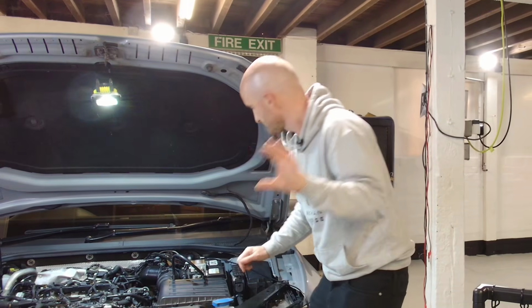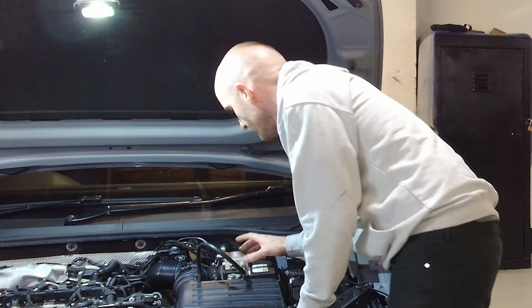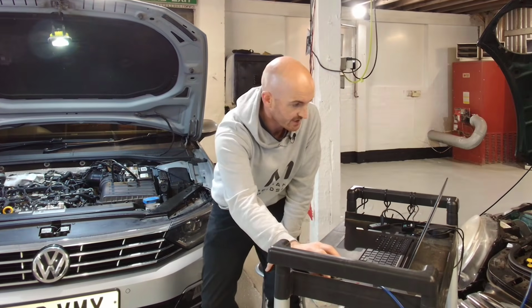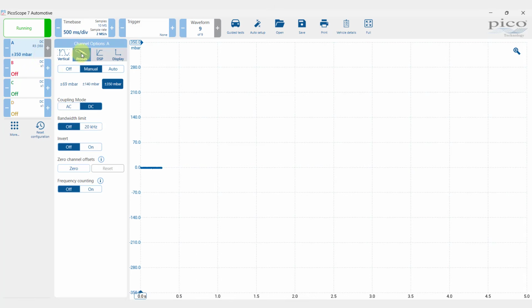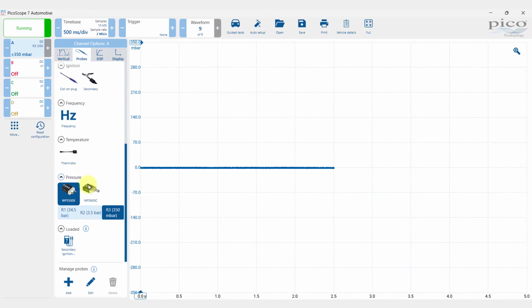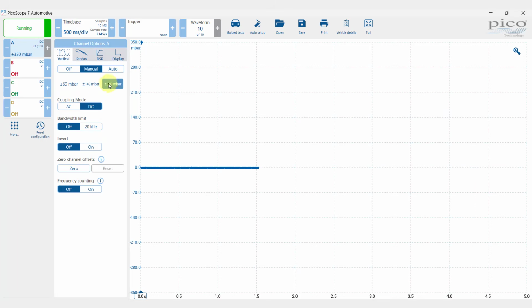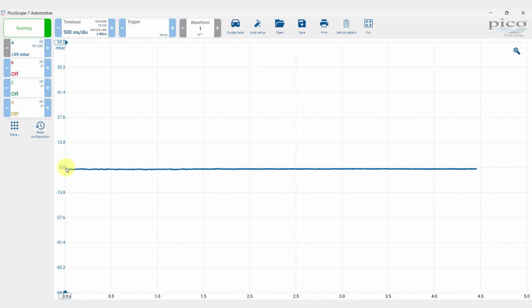Because this is going to be quite a low pressure, I'm going to put it on range 3 and we'll see what we get. Let's check the probe is on range 3 - I think it is. It was a maximum of 350 millibar there, which we could see on this scale. However, we want the lowest pressure we can, so let's change it to the 69 millibar scale and crank it over to see what we get.